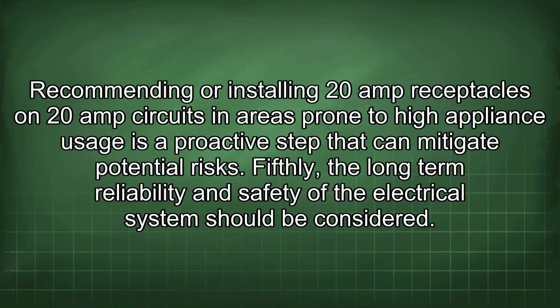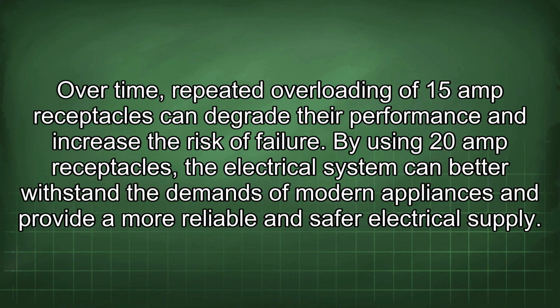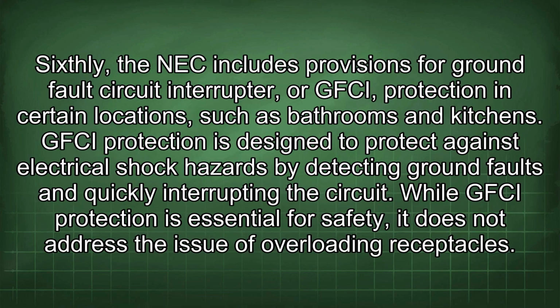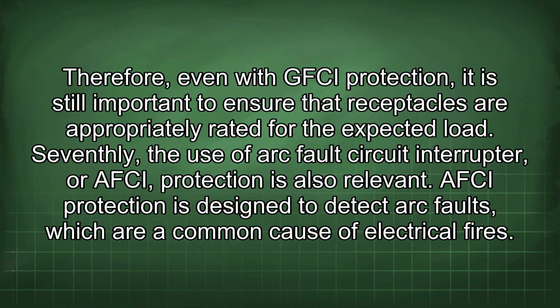Fifthly, the long-term reliability and safety of the electrical system should be considered. Over time, repeated overloading of 15 amp receptacles can degrade their performance and increase the risk of failure. By using 20 amp receptacles, the electrical system can better withstand the demands of modern appliances and provide a more reliable and safer electrical supply. Sixthly, the NEC includes provisions for ground fault circuit interrupter, or GFCI, protection in certain locations, such as bathrooms and kitchens. GFCI protection is designed to protect against electrical shock hazards by detecting ground faults and quickly interrupting the circuit. While GFCI protection is essential for safety, it does not address the issue of overloading receptacles. Therefore, even with GFCI protection, it is still important to ensure that receptacles are appropriately rated for the expected load.